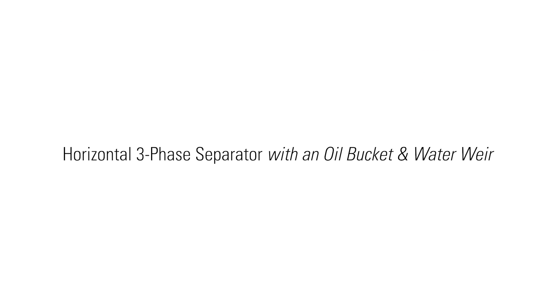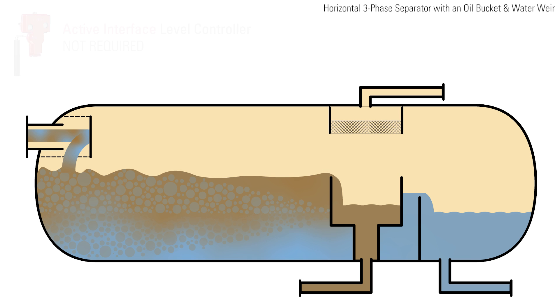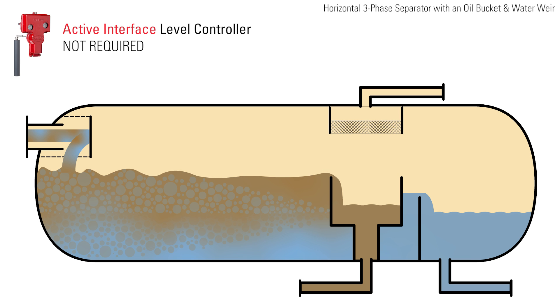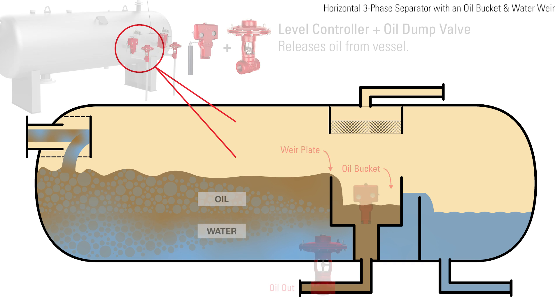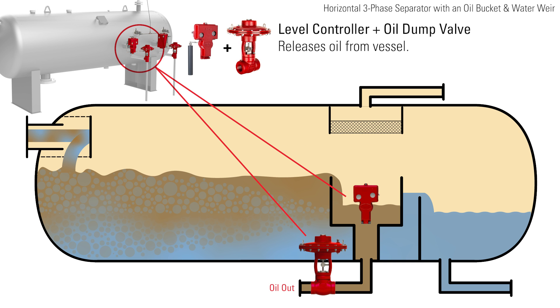In a horizontal three-phase separator with an oil bucket and water weir, the vessel does not require an active interface controller. As the oil separates on top of the water, it spills over the weir plate and into the oil bucket. The oil level in the bucket is controlled by a level controller sending a signal to the oil dump valve.